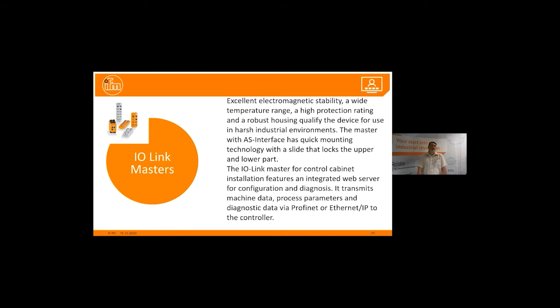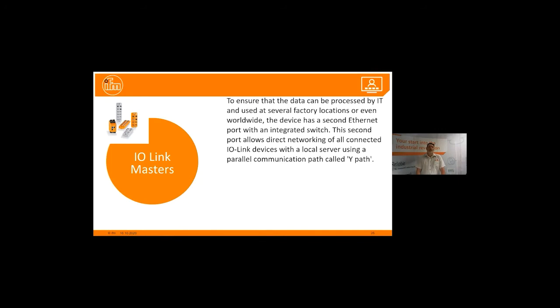As mentioned there on top, with the splitting and the mounting of the ASI IO modules, we don't have that with the IO-Link Master. It's a sealed unit completely, and no need for connecting onto a cable, like with an ASI cable. It works on a network-based platform. To ensure that the data can be processed by IT and used at several factory locations or even worldwide, the device has a second Ethernet port with an integrated switch. This second port allows direct networking of all connected IO-Link devices with a local server using a parallel communication path that we call the Y path.